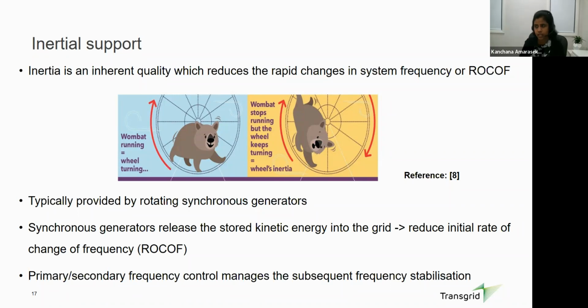Inertia is an inherent quality of the power system which reduces rapid changes of the frequency, or rate of change of frequency. I again took this analogy from AEMO to explain the concept of inertia. What we have here is a wombat running on a wheel, and let's say the wombat suddenly stops running, but the wheel will still keep on moving for some time. It's due to the wheel's inertia. Similarly, in power systems, this inertia is provided by synchronous generators. Synchronous generators release stored kinetic energy instantaneously to the grid to reduce the instantaneous rate of change of frequency. And usually other frequency control services in the network, such as governors or primary or secondary frequency control, come in later to manage the subsequent frequency stabilization.